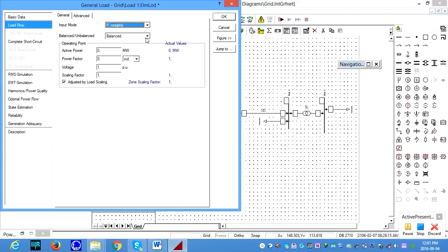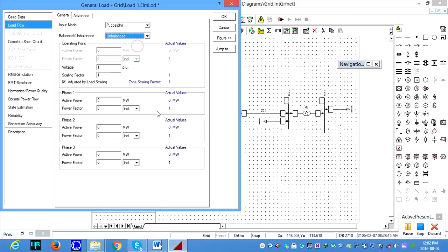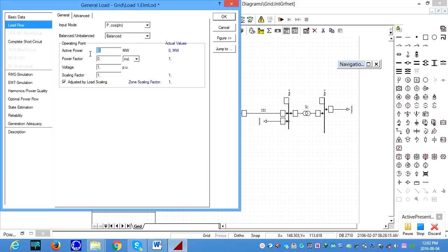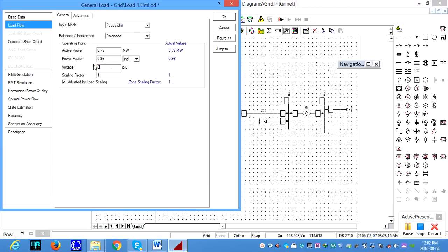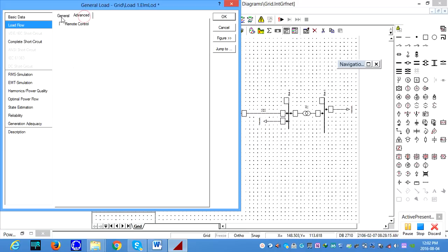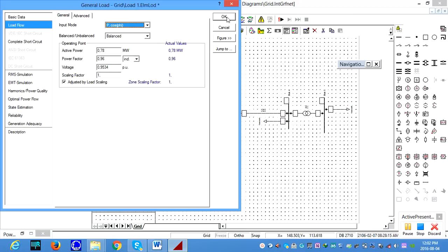And the load can be balanced or unbalanced. Balanced means we have the same loading capacities on each phase of the lines, or if we select unbalanced, we should be able to load different loading capacities on each phase. But in this case, we used a balanced load. So the active power of the first load is 0.78 megawatt. And the power factor is maintained at 0.96. And the voltage set point, we're trying to make 0.9534. Okay, that's all the data. In Advanced, there is a remote control, but we're not playing around with those things for this exercise.